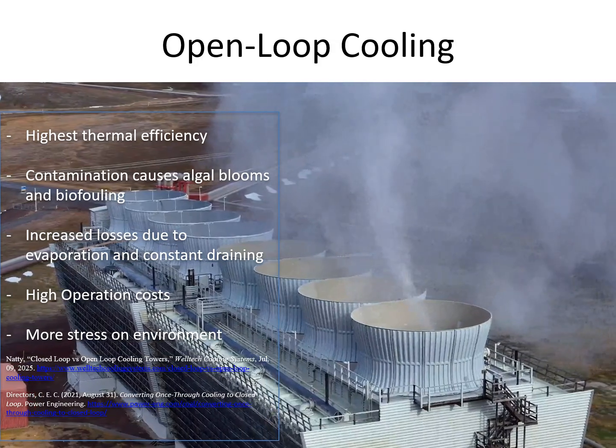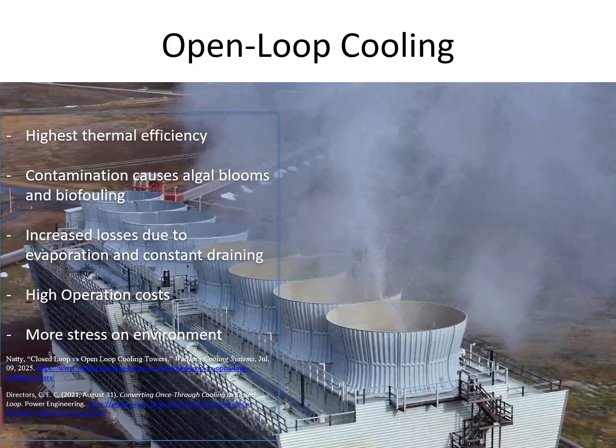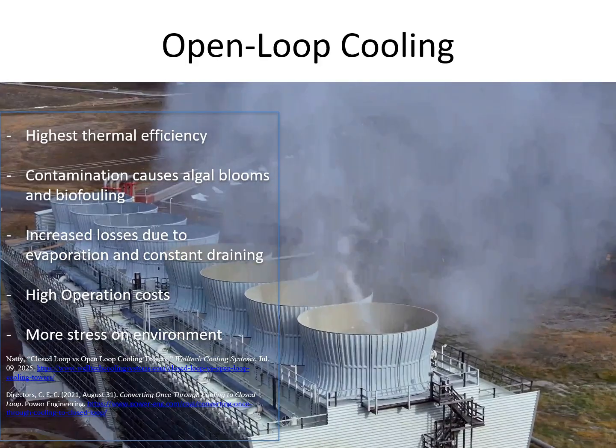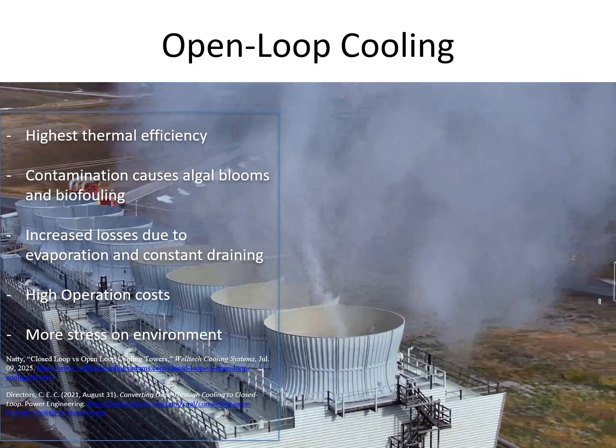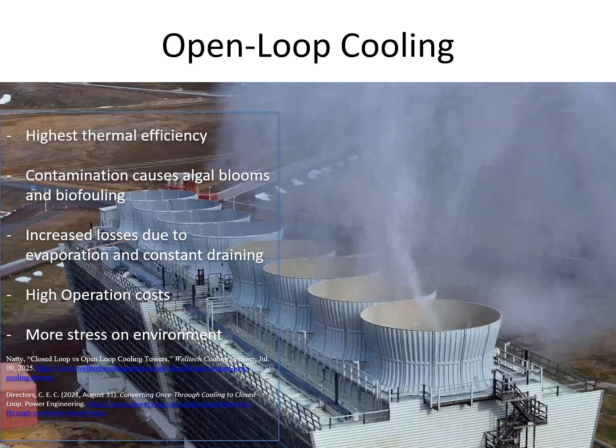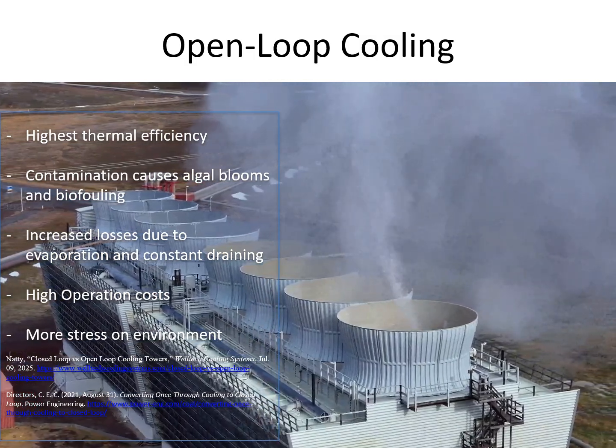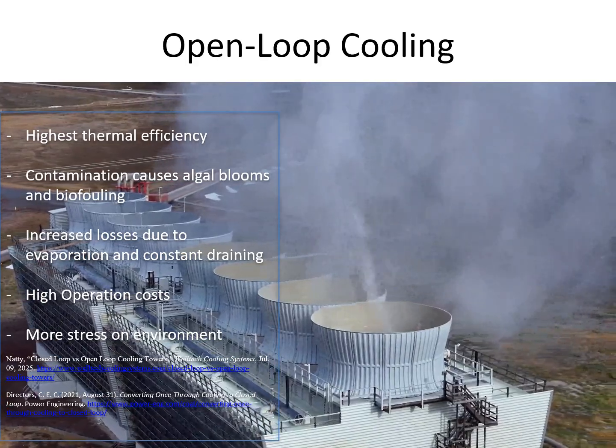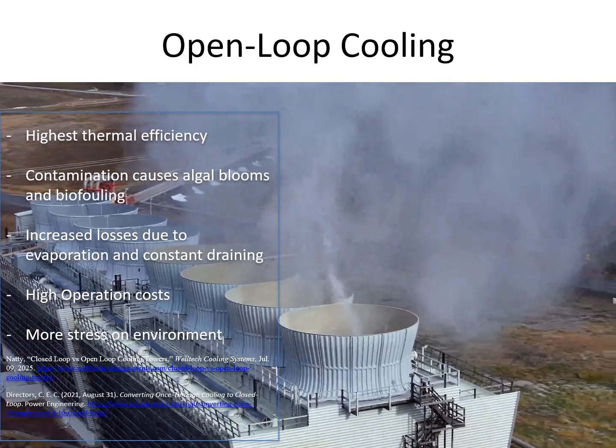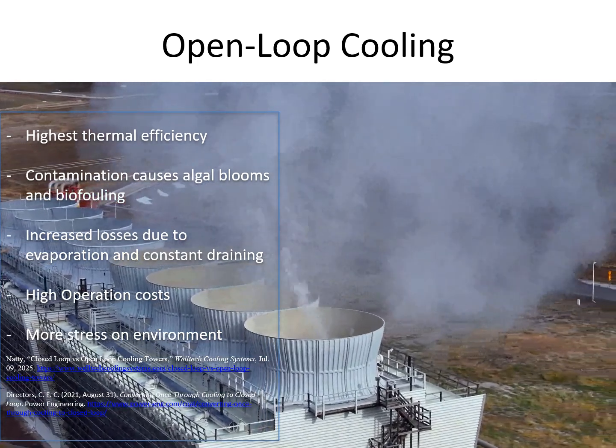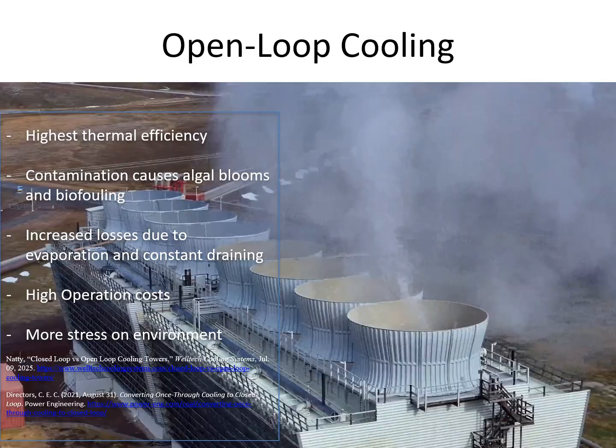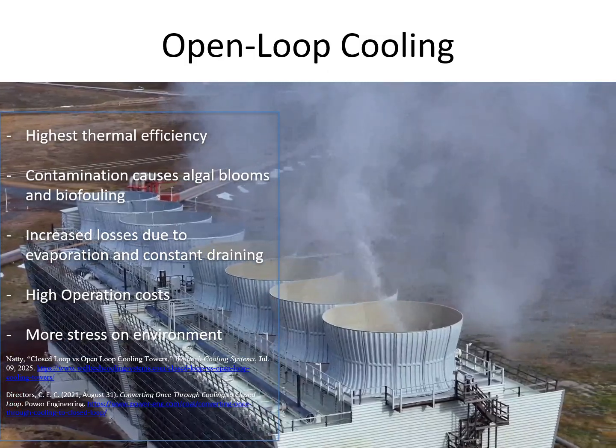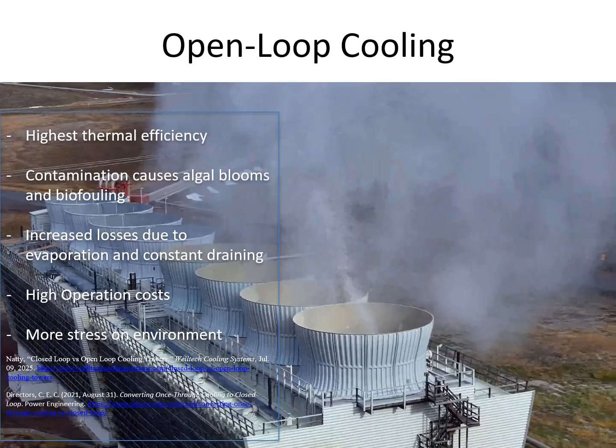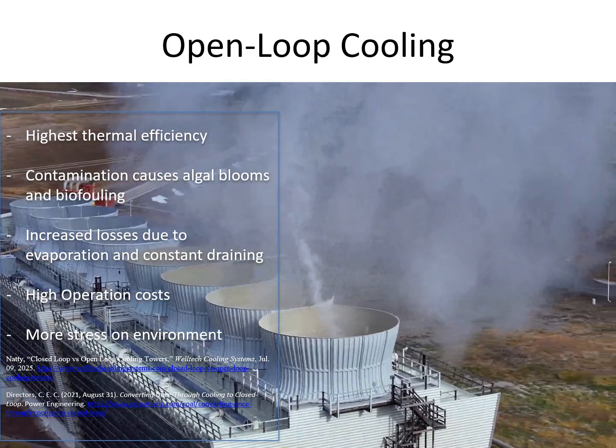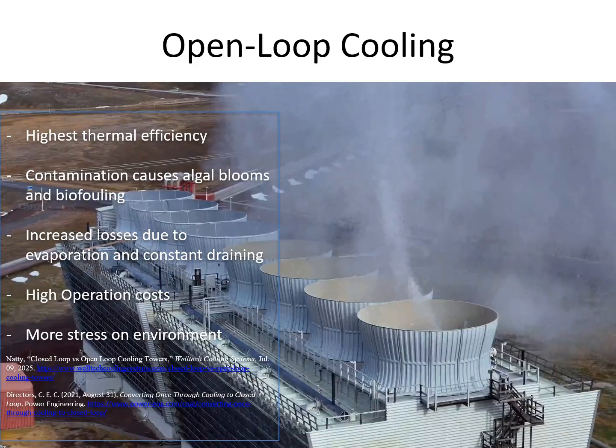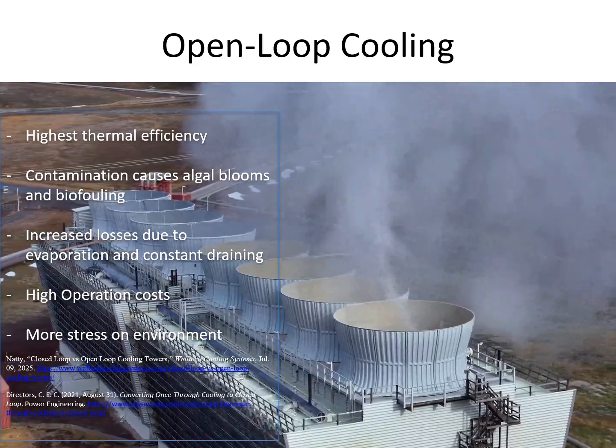Open-loop systems are very efficient at providing cooled water to be used in the process, but there are many drawbacks. Due to the evaporative process, the conductivity in the water can rise, causing serious damage to the piping. To mitigate this highly corrosive water, a portion must be constantly drained or blown down and refilled with fresh water, which puts excessive strain on the main water source. Water in this system is also open and exposed to dust, debris, and biological growth. These contaminants must be chemically treated. Due to the high chemical content in the treated water, what is drained can be toxic to the environment and must be disposed of properly. Although this system works well, the open-loop system consumes a significant amount of water and threatens the water security of local communities, especially those in drier climates.